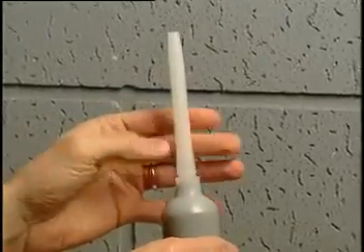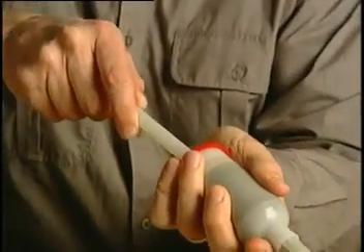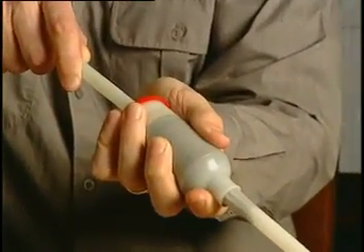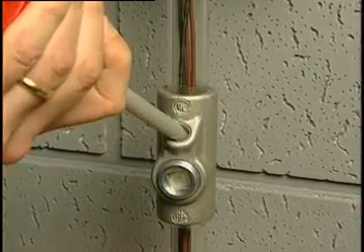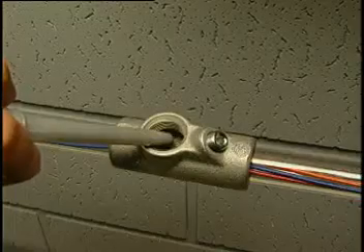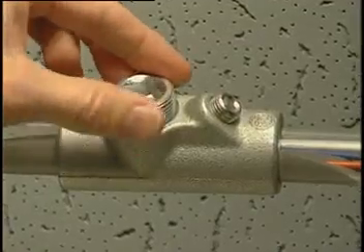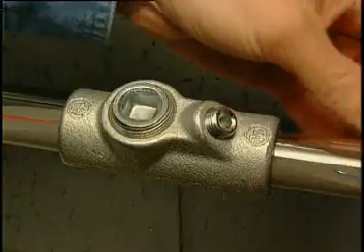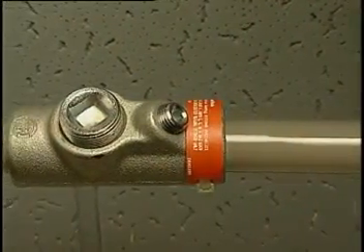Screw in the nozzle where the mixing rod was. Gently push the end cap with the mixing rod. This will disperse the Chico Speed Seal compound. Fill a vertical seal up to the bottom of the smaller plug and no more than halfway on a horizontal seal. Replace the seal plug, strap the label around the fitting and your seal is now completed. It's as simple as that.